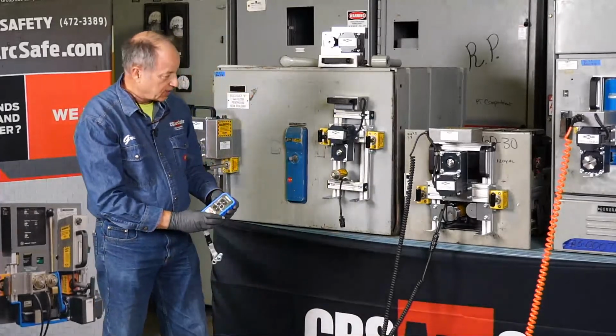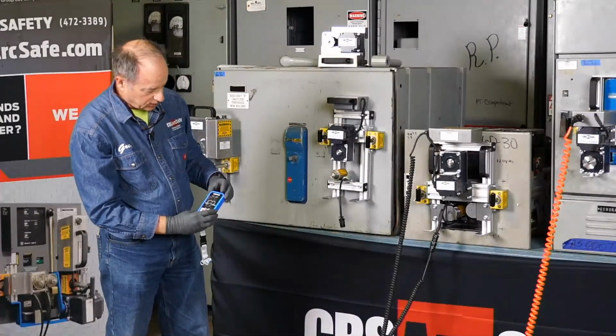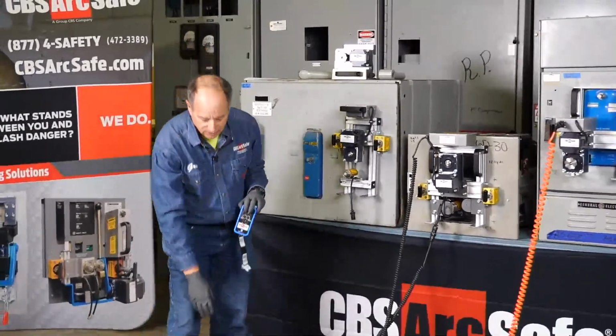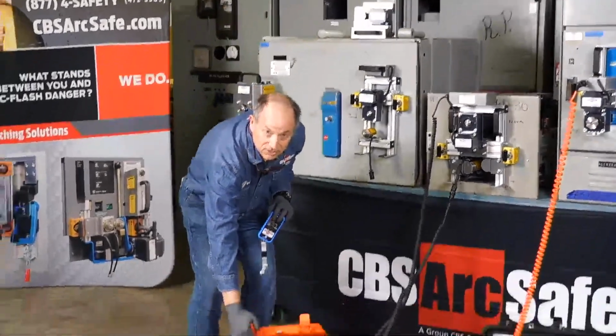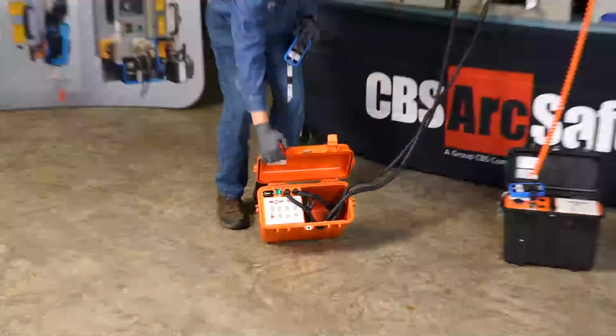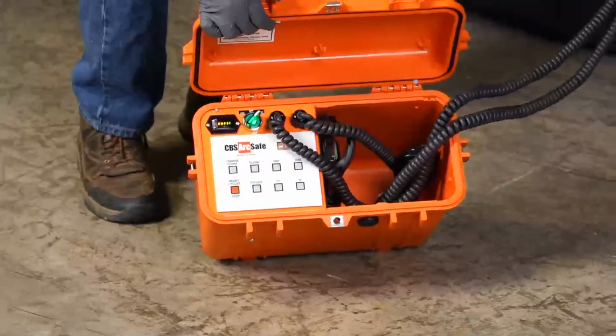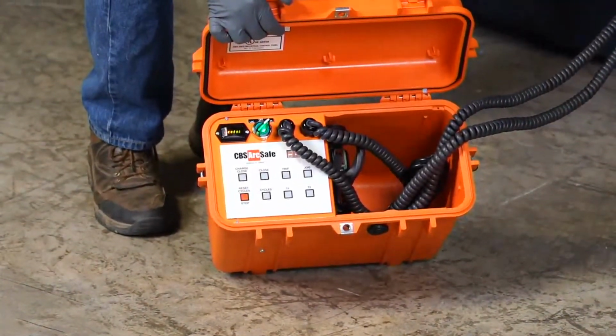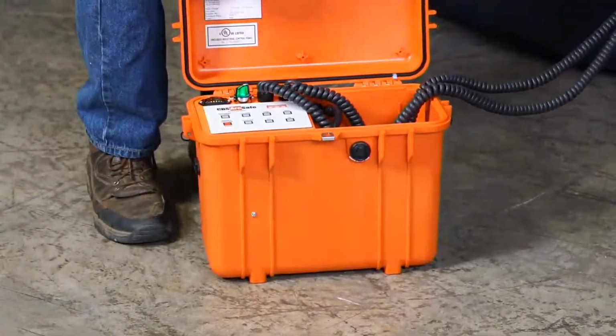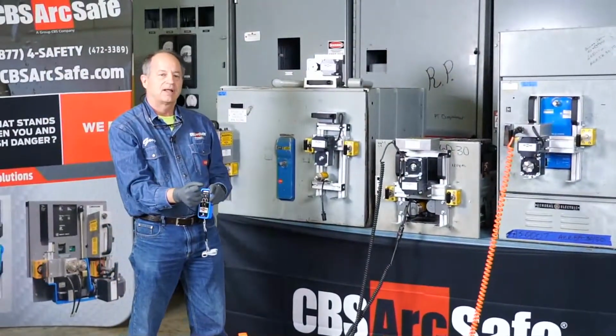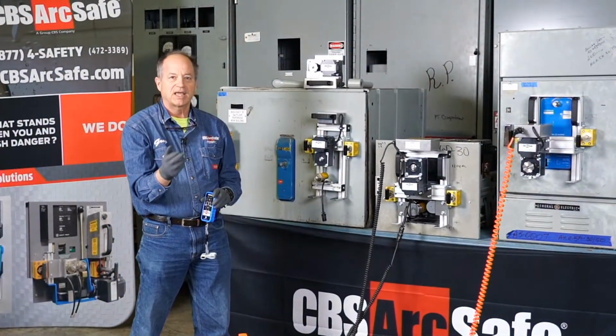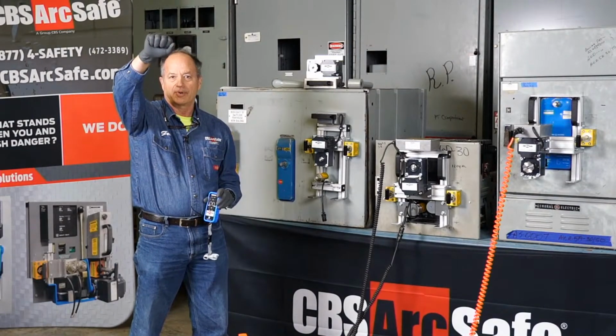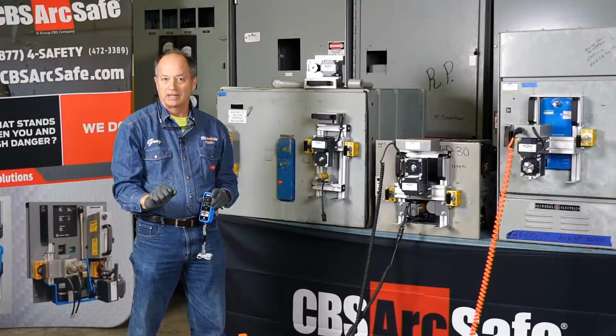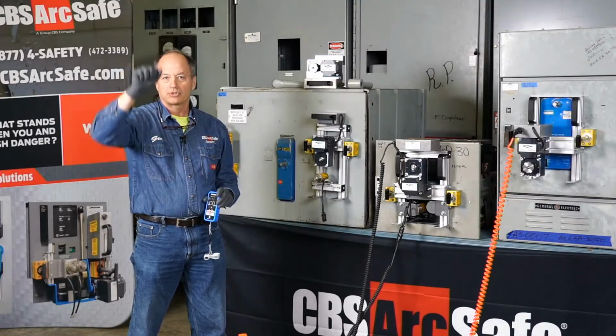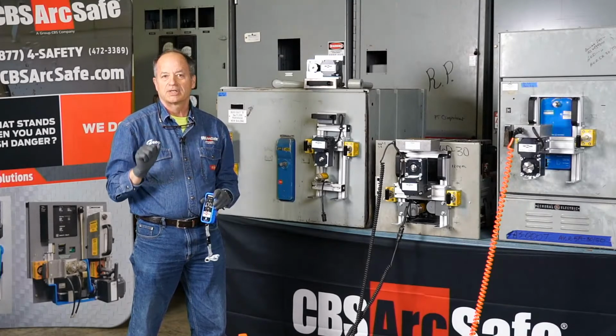Now for this, we're going to have 3 buttons we're going to use. We're going to use charge close. And the reason we have the system here labeled charge close, just to discuss this for a second. When we came up with this, we had a whole different types of breakers to work with. You have some of the first generation of GE breakers, like the GE AK1, where I move the handle up, I bring the handle down, and the breaker closes at the bottom of the stroke. ITE K-lines do this, where you take a manually operated K-line, you pull that black handle down, and boom, it closes at the bottom of the stroke. So you were both charging and closing the breaker in a single action.